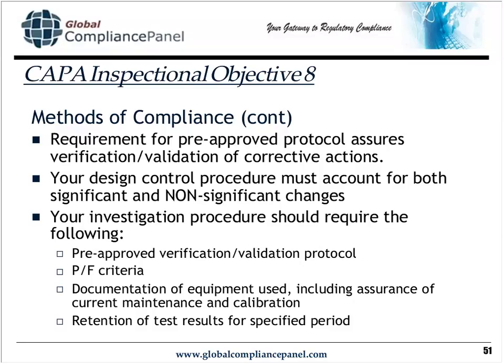Your investigation procedure should make sure, again, pre-approved verification or validation in a protocol, pass-fail criteria, very important. That pass-fail criteria has to be measurable. It can't be preferences. I don't mean measurable, I mean it has to be absolute. It can't be preferences. It has to be a requirement.